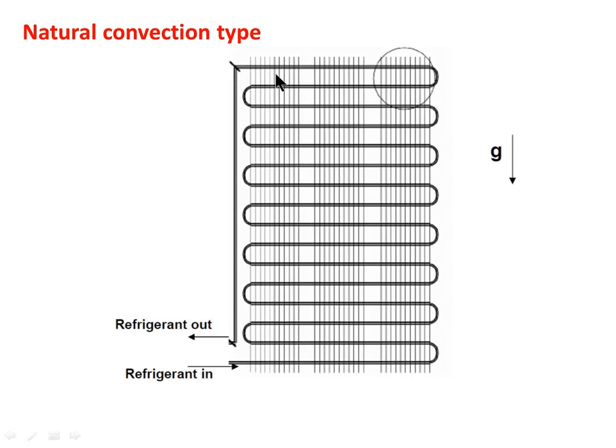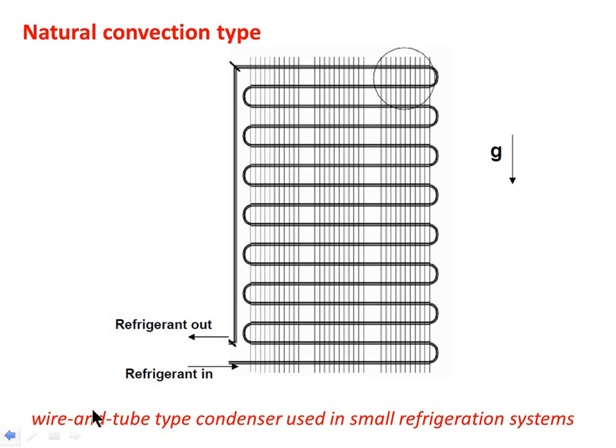First, the natural convection type condenser. This is the diagram for the wire-and-tube type condenser, which is generally used in small refrigeration systems. Here we can see the refrigerant inlet and refrigerant outlet. The wires are nothing but fins provided over these tubes. These types of condensers are generally used in domestic refrigerators. There is no other medium of heat extraction, so this is an air-cooled condenser only.